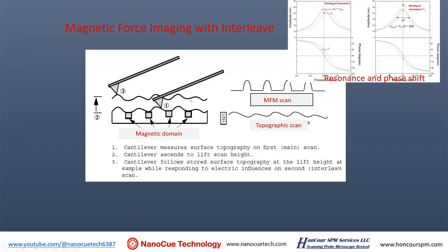The lift distance is typically about 15 nanometers, sometimes 100 nanometers. If the sample is extremely smooth, you could lift a shorter distance. If the sample is very rough, you need to lift a higher distance, because if you lift too short, the tip will collide with the sample and you'll mix the MFM image with your topography image, and the MFM image will no longer look purely like MFM.